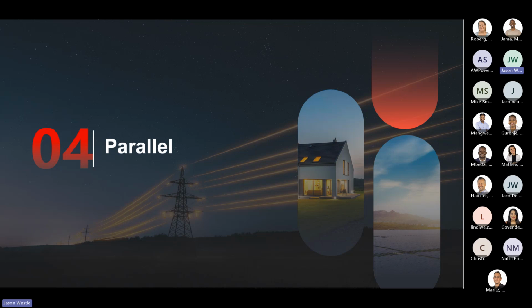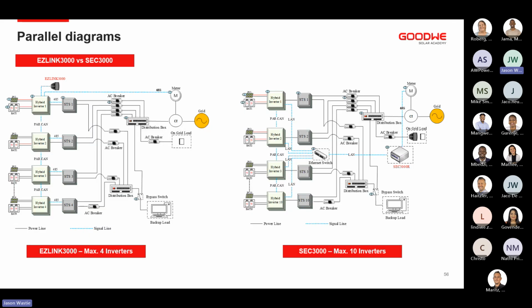Again, this is what differentiates the ET50 from the previous ET15 to 30. The ET50 can parallel, whereas unfortunately the previous could not. There are two scenarios when we get to paralleling systems. There is the EZLINK3000, where you can have a max of 4 inverters connected. And then if you want to go even bigger, you can go up to 10 inverters connected with the SEC 3000C. The difference is that with the EZLINK3000 or up to 4 inverters, you'll have your UPS level switching, and with the bigger connection, obviously it will take slightly longer.